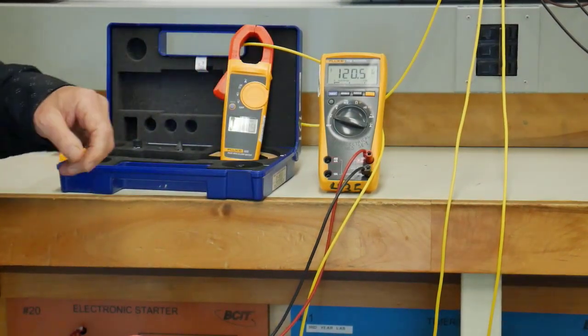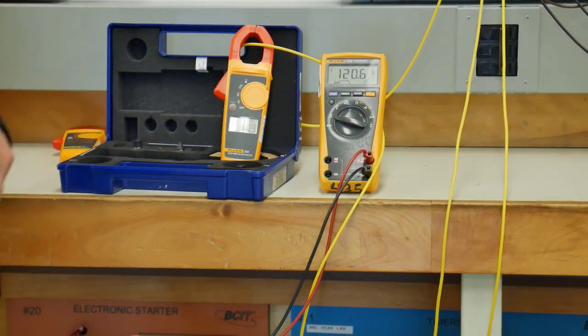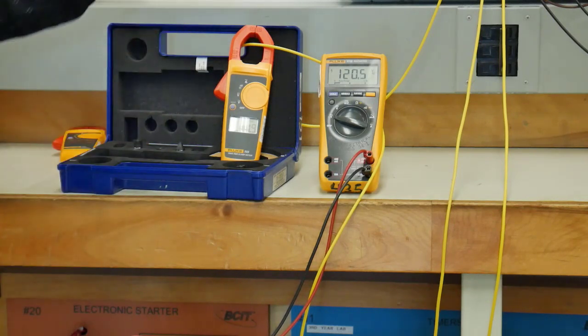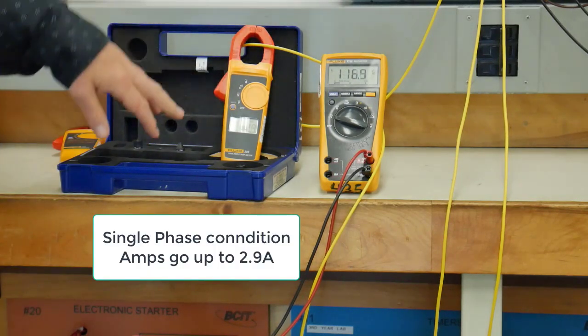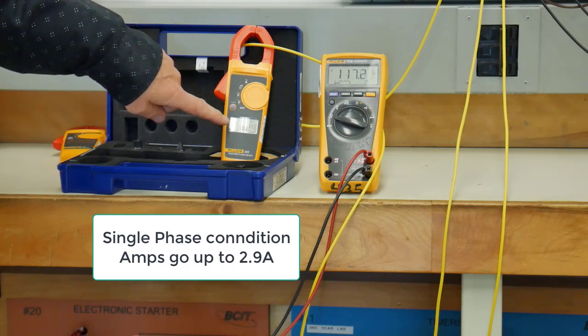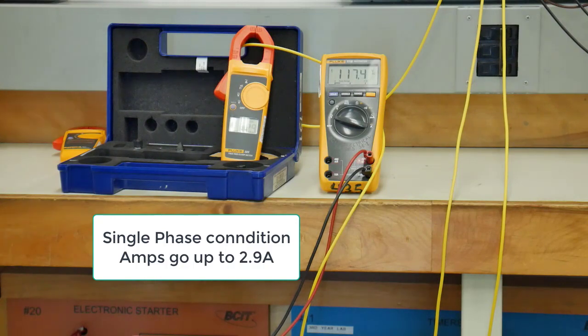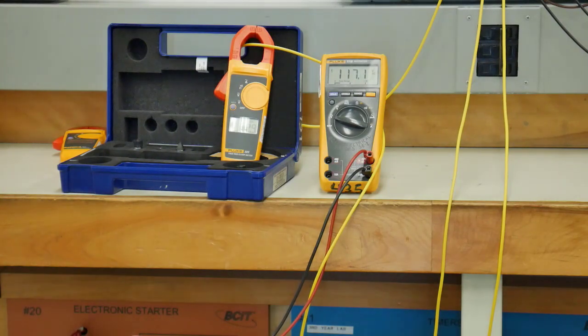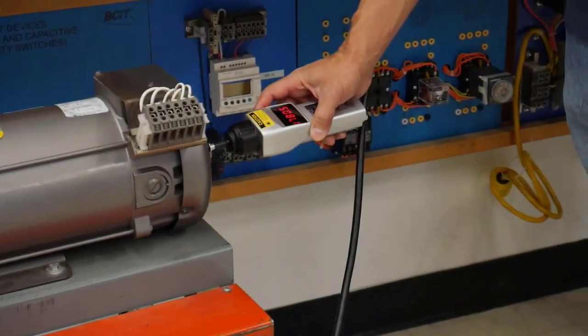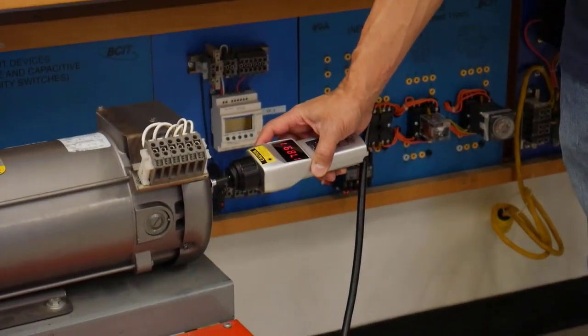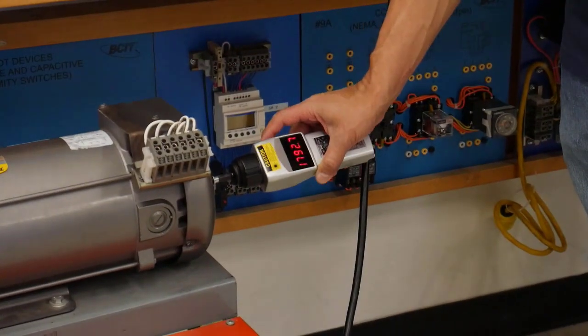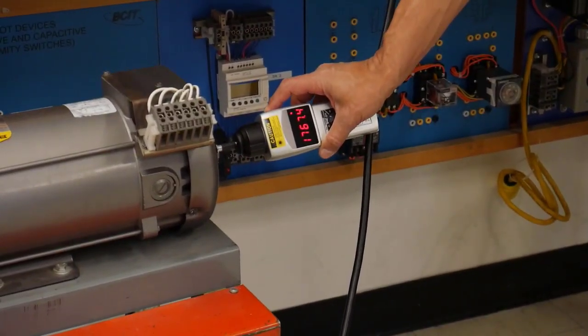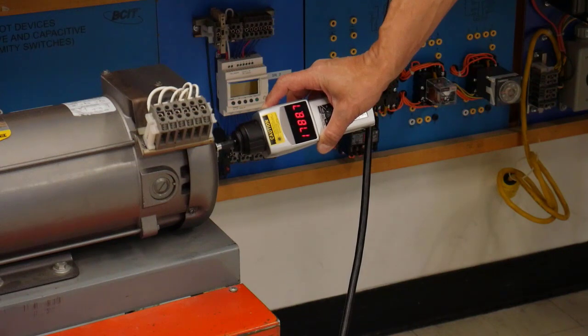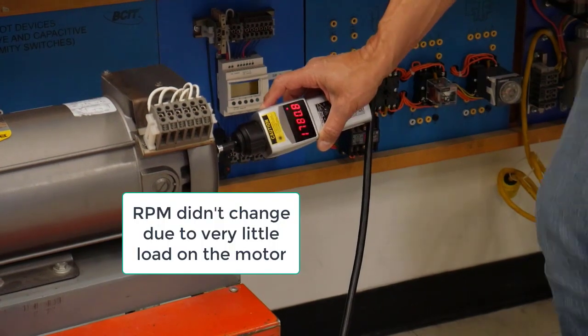Let's have a look at our current reading. We're going to create our single phase condition now. Our voltage dropped a little. Our current has gone up from about 1.7 up to 2.9, and our RPM is about 1788. It hasn't really changed at all.